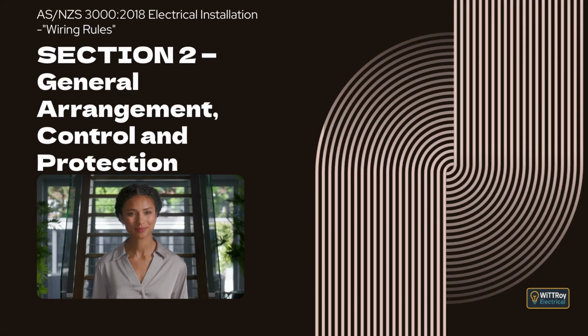Where the conditions are suitable, a group of circuits may be isolated by one common switch. This helps when circuits work together or feed one piece of equipment. Any means of isolation must make sure the equipment cannot become live by accident. The isolation device must need a deliberate action to re-energize the equipment. Extra precautions may be used, such as fitted padlocks, warning tags, lockable spaces, or short-term earthing. These measures help prevent someone from accidentally switching the supply back on.